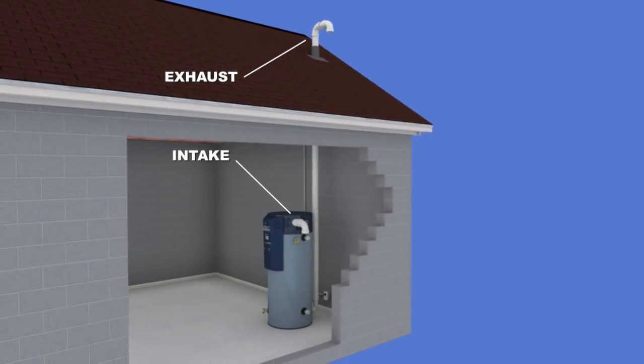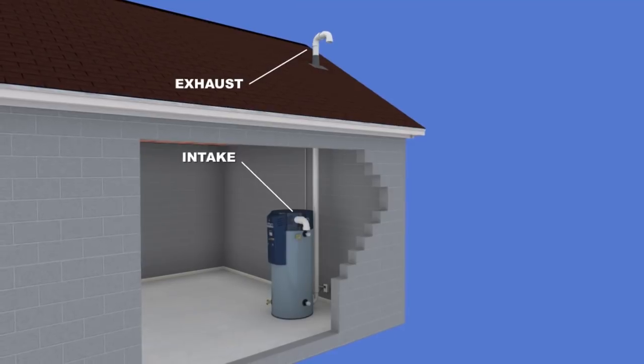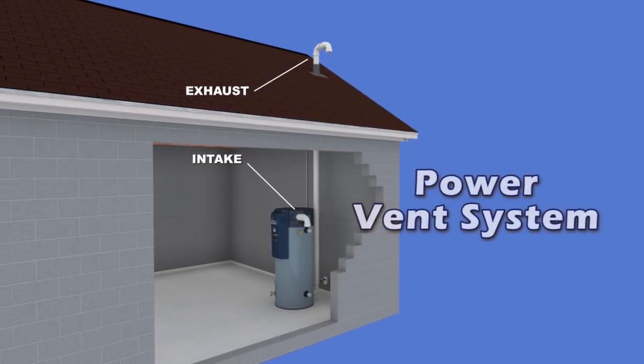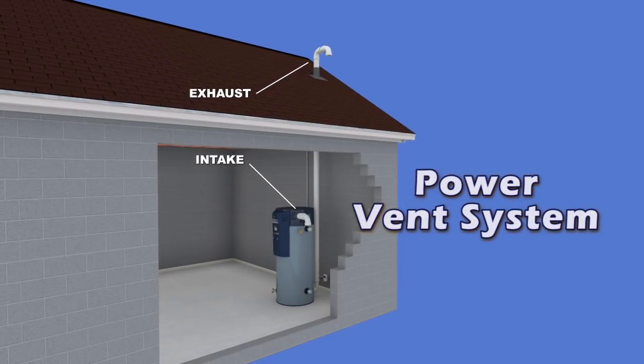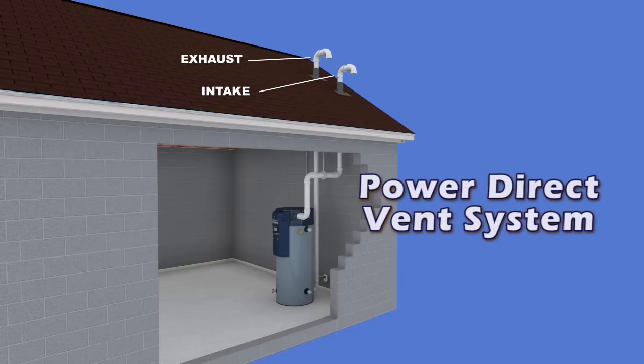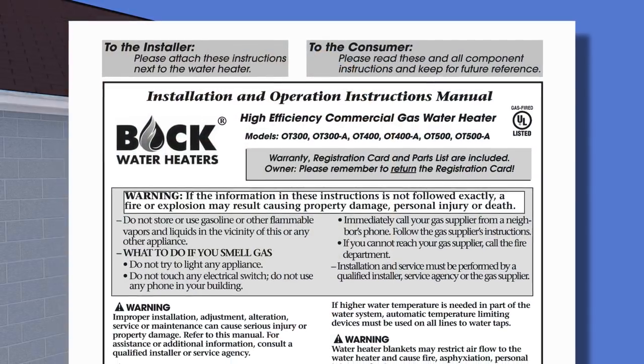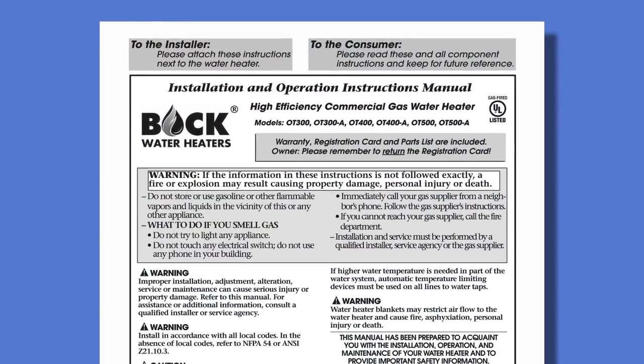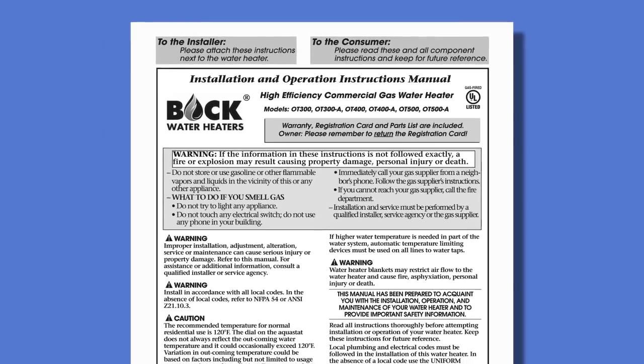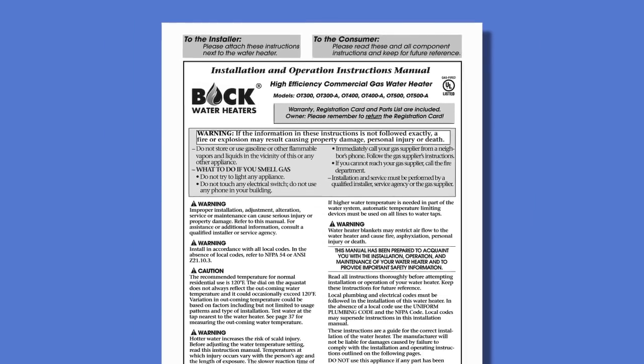Once the location is decided, the source of combustion air is selected. The water heater can be installed to utilize combustion air from either inside the building, a power vent system with a single exhaust vent, or from outside the building, a power direct vent system with an exhaust vent and an intake vent. Failure to familiarize yourself with the proper installation of the vent and combustion air intake system outlined in the manual can result in unsafe operation of the water heater.